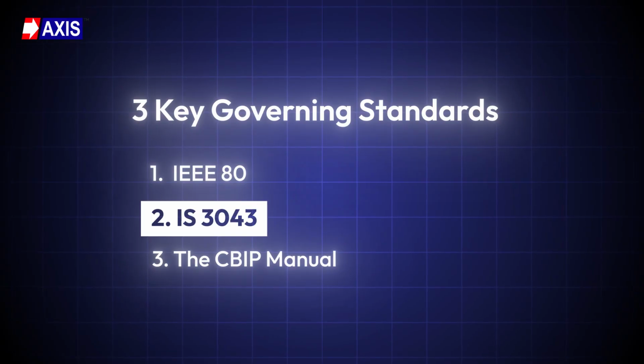While IEEE 80 is the global standard for substation earthing, you will always have local codes and local standards that are as per your requirements. In India, we have IS 3043, which is the Indian Code of Practice for Earthing. It provides guidance on earthing methods for land-based electrical installations in India, covering everything from system earthing to equipment earthing across different supply configurations.